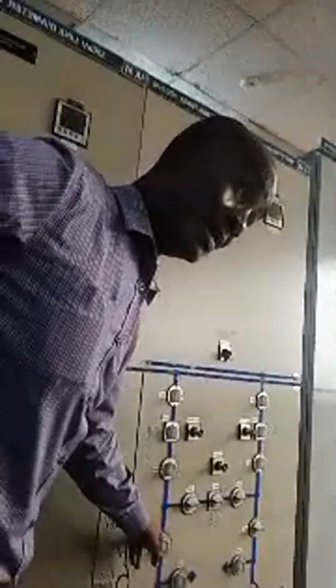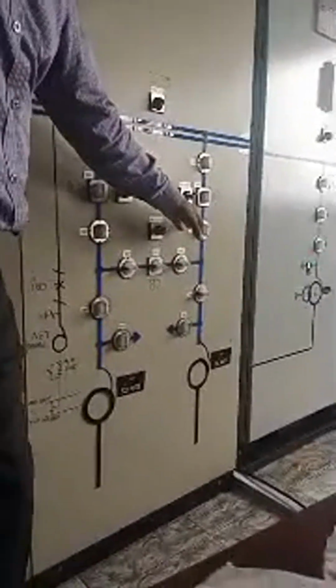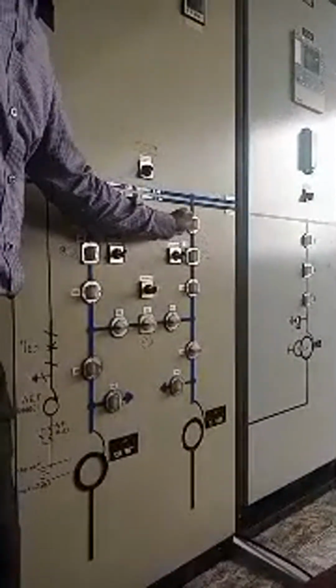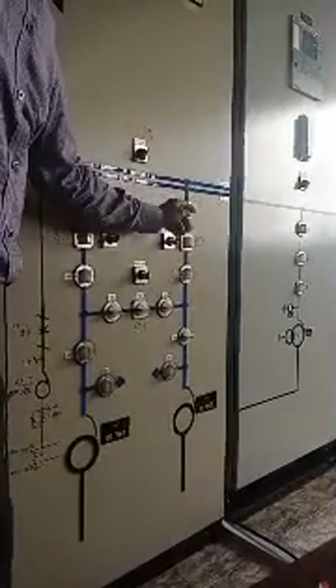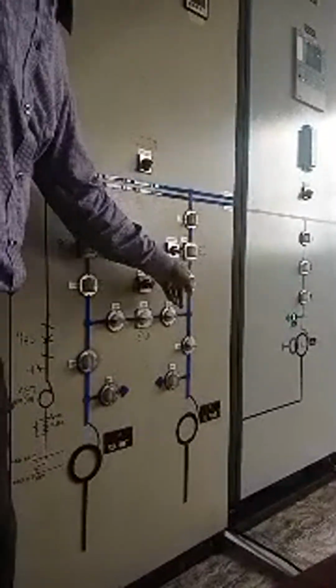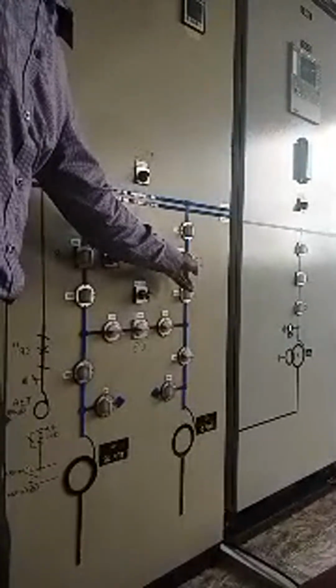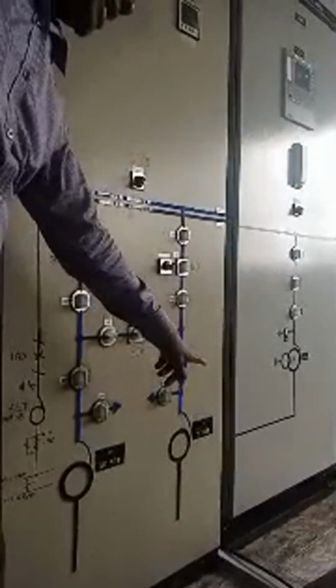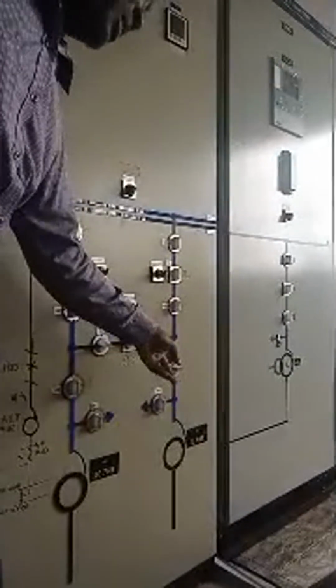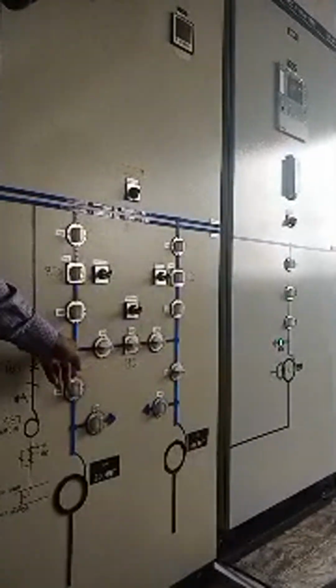This tie CB, assuming now that this future is in place, we will move this supply and come back to this. In other words, assuming this very breaker has an issue or there is maintenance going on, you take out this breaker and use these two isolators to isolate this CB. So Onisha can still be getting supply from us through this place as long as this breaker is on, through bus bar 2.